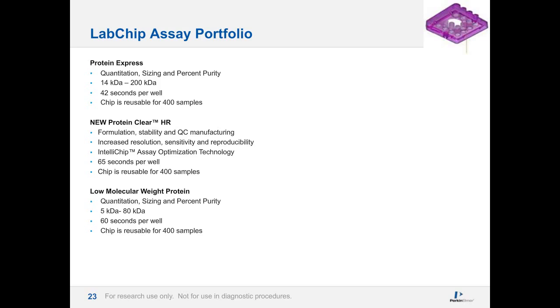In total, our assays are tailor-made for different applications to fit into each stage of your process. The Protein Express assay is used for quantitation, sizing, and percent purity from 14 to 200 kilodaltons — our highest throughput assay at 42 seconds per well. The low molecular weight protein assay is similar but optimized for proteins from 5 to 80 kilodaltons at 60 seconds per well to achieve resolution at lower molecular weights. All chip types are reusable for up to 400 samples.